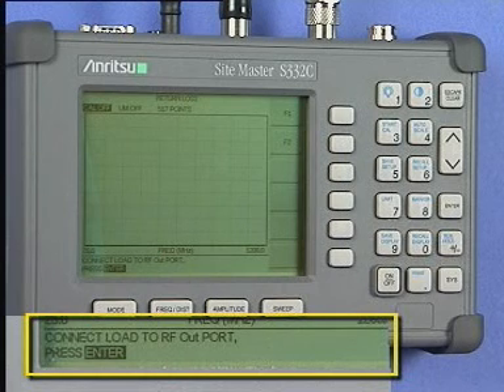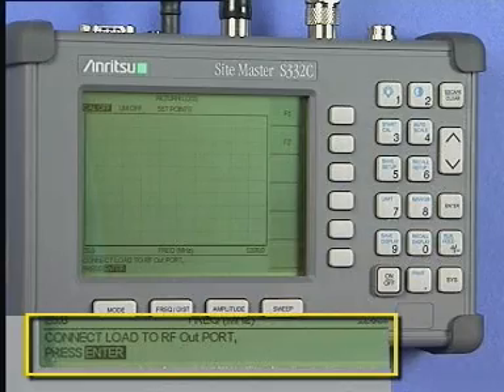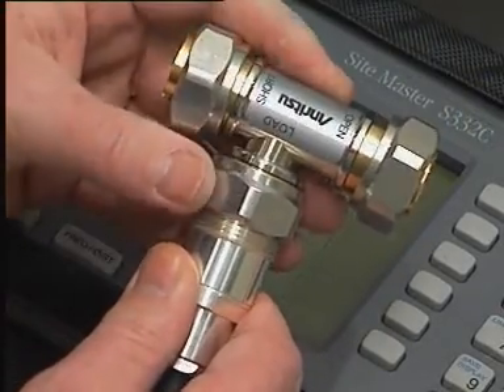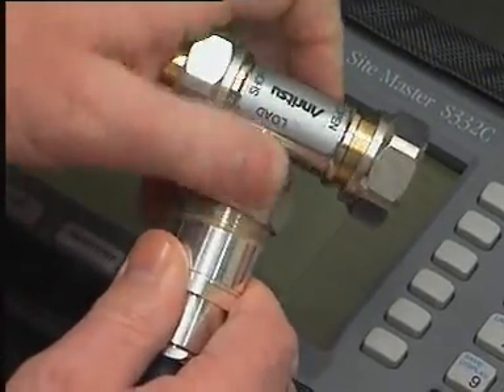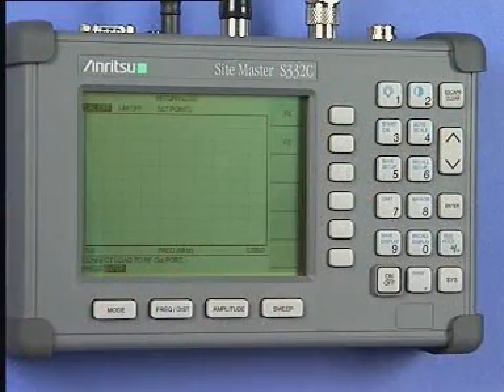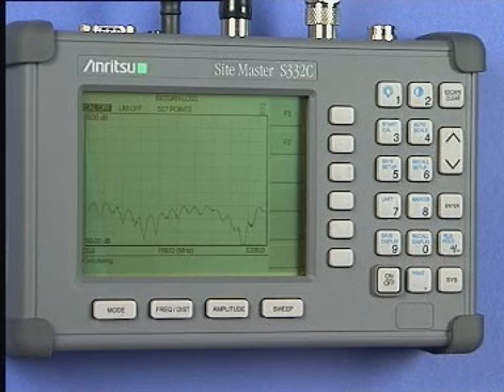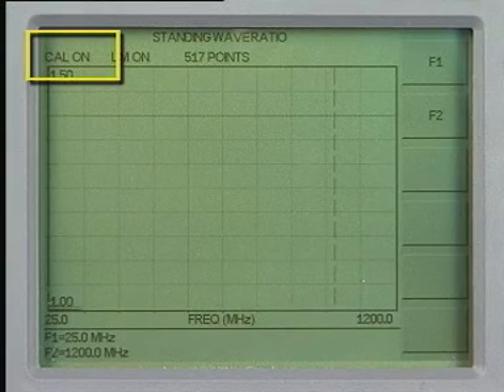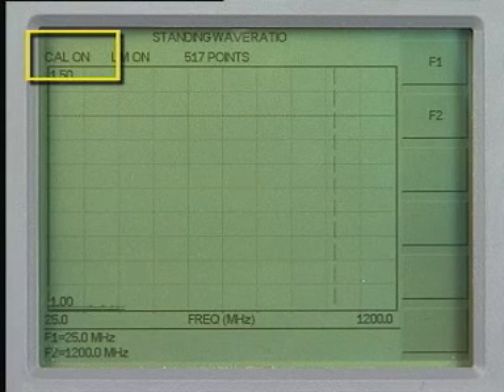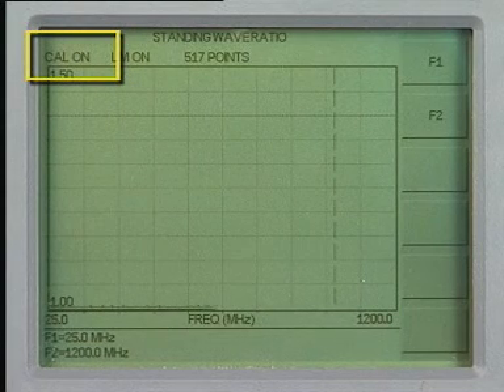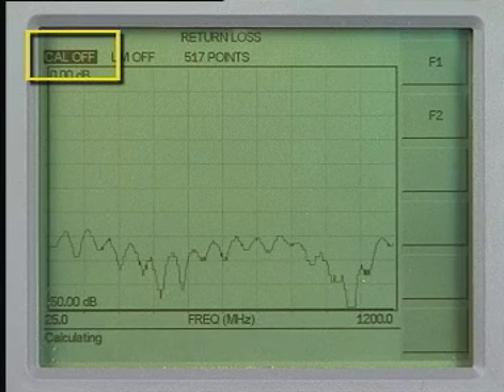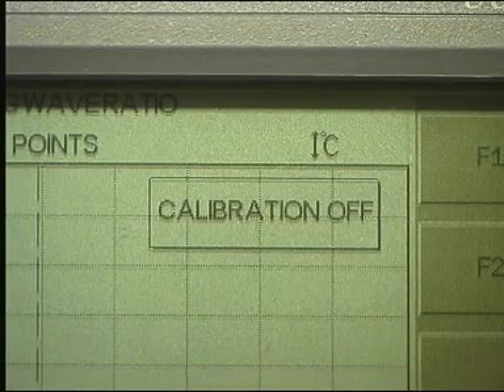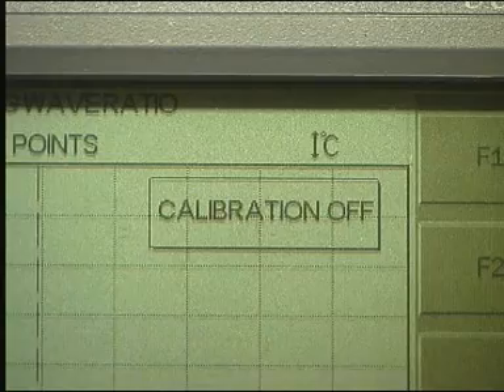After a few moments, the Sitemaster will prompt you with another message, Connect Load to RF out, which is asking you to connect the calibrated 50 ohm dummy load. When you have done this, press the Enter key and the instrument will once again sweep and measure. Now you will see the message Cal On at the top left of the screen. If the instrument was not calibrated, then you would have seen the message Cal Off, as well as a very, very large calibration off warning box in the middle of the display. Harry, take note.